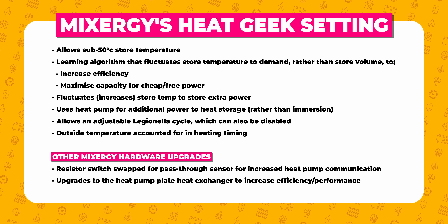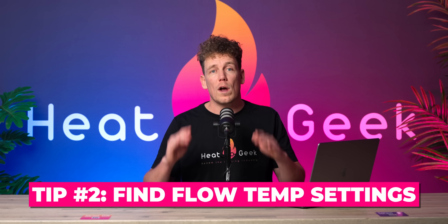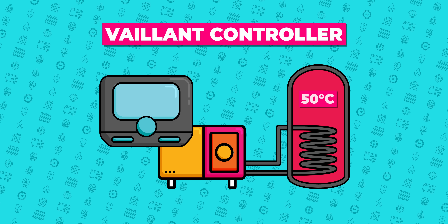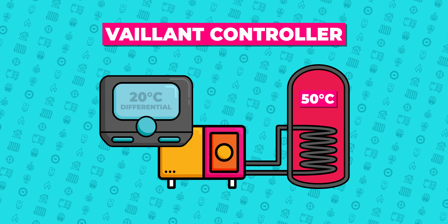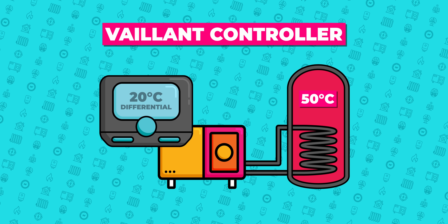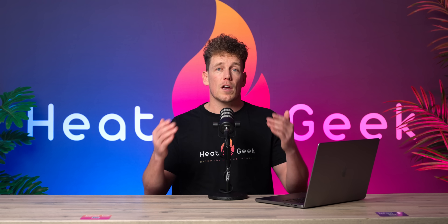Visit Mixergy's website to find out more details in the description. So that's the first point: minimize the store temperature. Next, look for your target flow temperature setting from the heat source when in hot water mode. In the Vaillant, you can set your target temperature differential — so if your cylinder temperature is set to 50 degrees C and your differential temperature is set to 20 degrees C, then your heat pump would try to target 70 degrees flow temperature throughout the entire heat-up of the cylinder. I've turned mine personally down to zero to make sure the heat pump holds back and stays cooler.